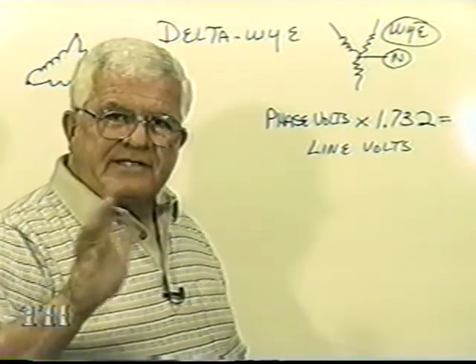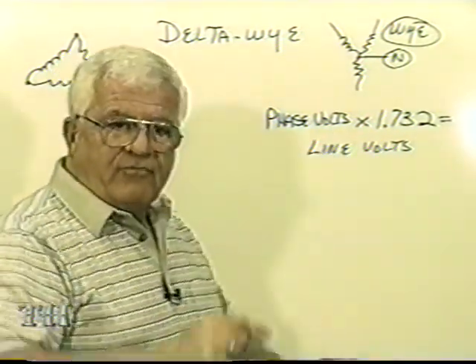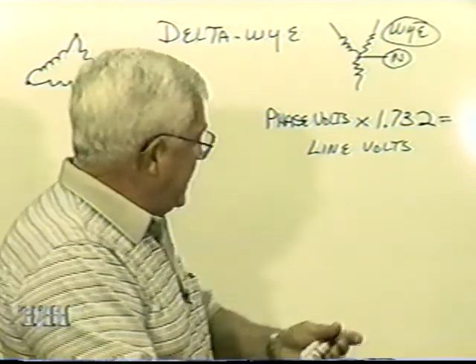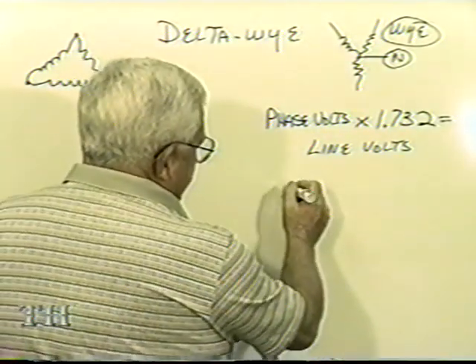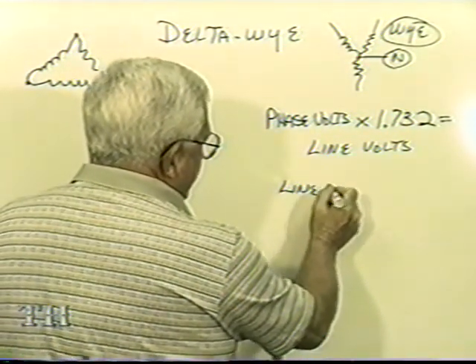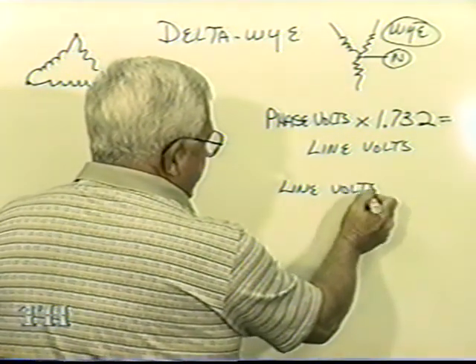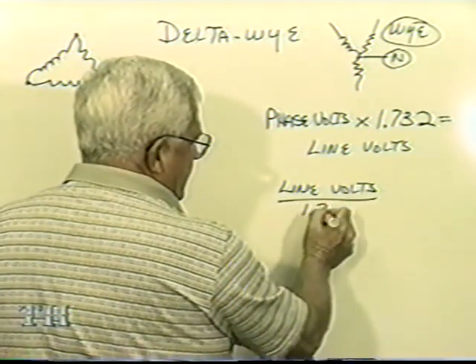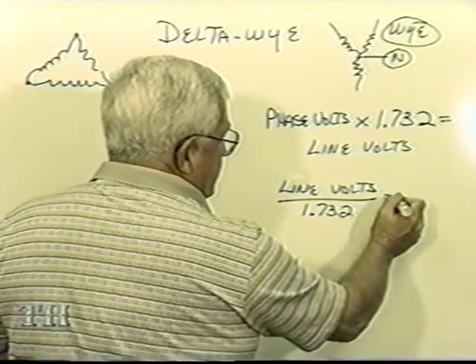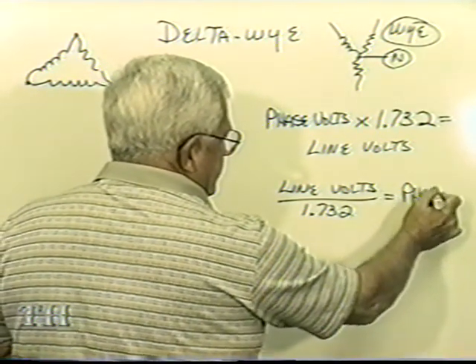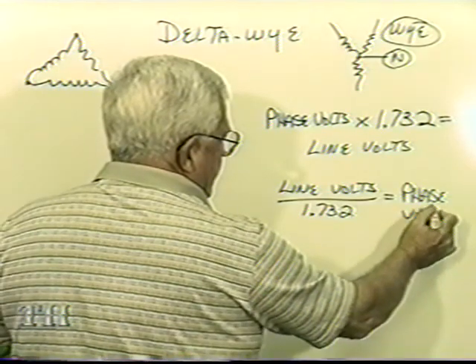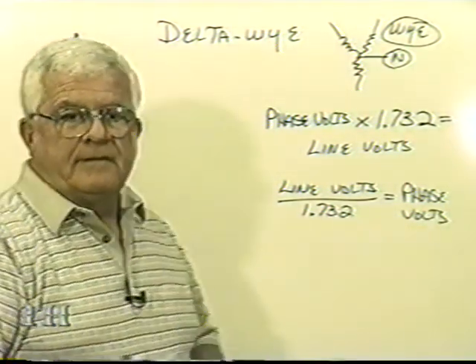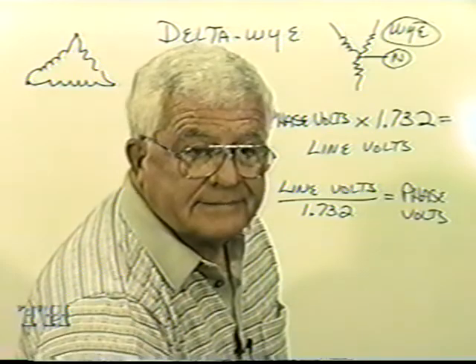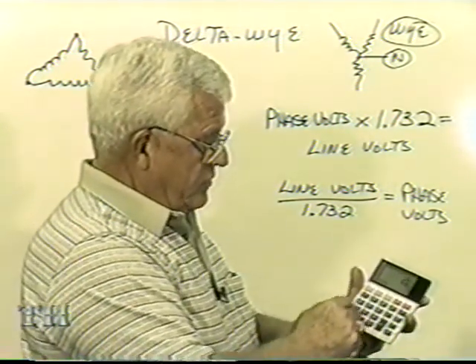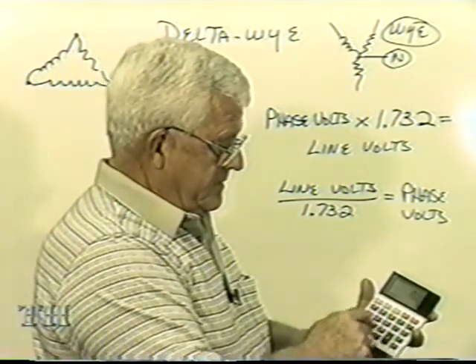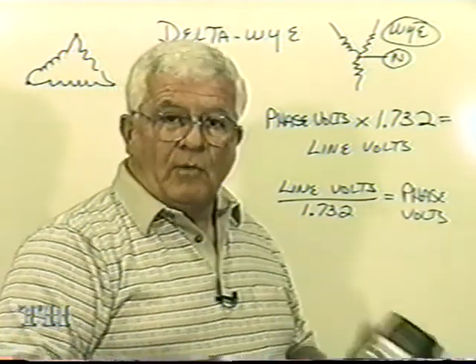Now, here's where that's so important. If I take this same format and just flip it over, for example, say I take the line volts and I divide that by the square root of 3. That's going to put me back to phase volts. If you have your calculator, you say, well, that makes sense. If I take 208 and divide it by 1.732, it gives me the 120 volts.